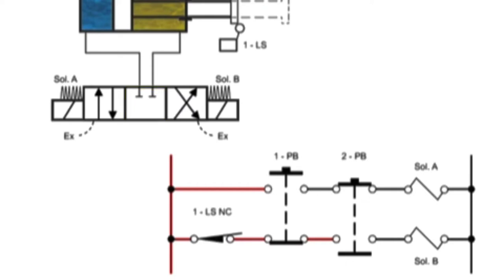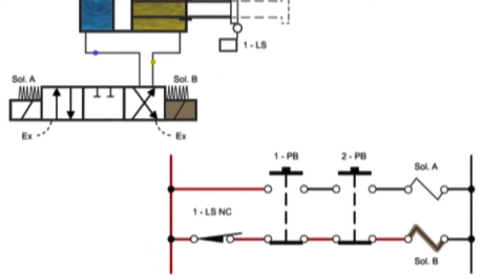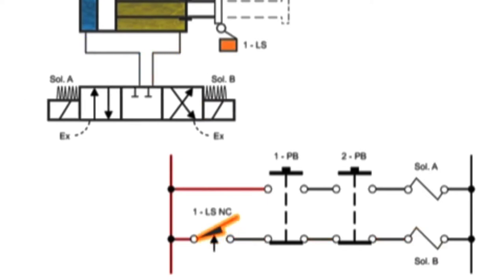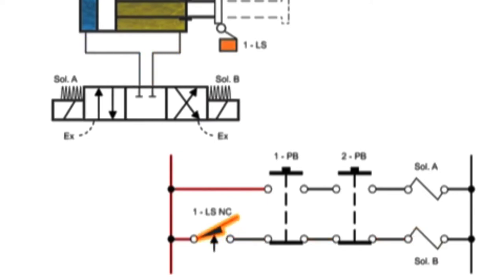If both buttons are released while the cylinder rod is extended, limit switch one allows solenoid B to become energized. The valve will shift to allow fluid into the rod end of the cylinder, causing it to retract. When it reaches the end of its stroke, it engages the limit switch, which opens the circuit and prevents electricity from flowing until the two start buttons are engaged once again.